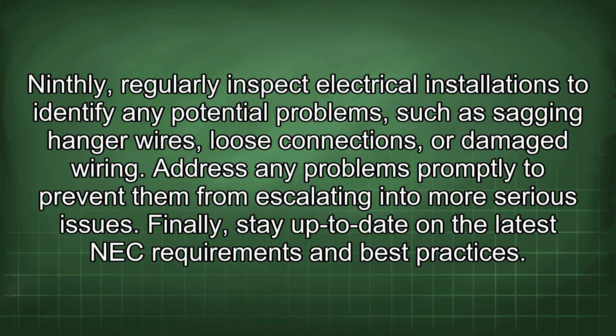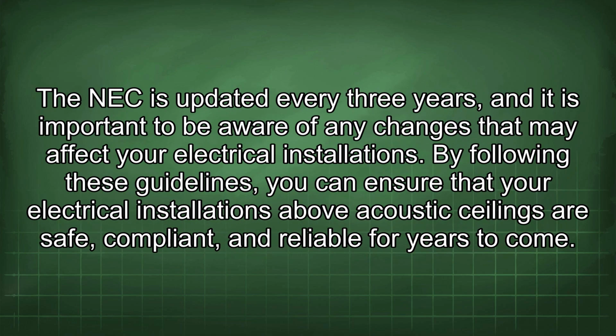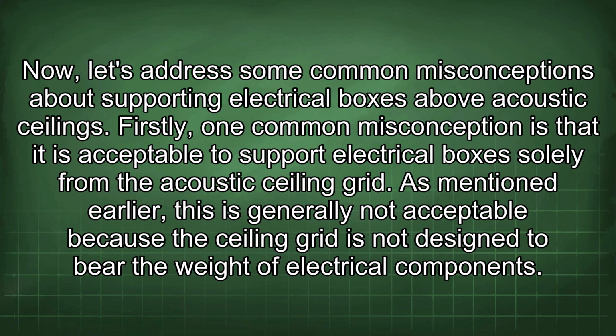Finally, stay up to date on the latest NEC requirements and best practices. The NEC is updated every 3 years, and it is important to be aware of any changes that may affect your electrical installations. By following these guidelines, you can ensure that your electrical installations above acoustic ceilings are safe, compliant, and reliable for years to come. Now, let's address some common misconceptions about supporting electrical boxes above acoustic ceilings. Firstly, one common misconception is that it is acceptable to support electrical boxes solely from the acoustic ceiling grid.